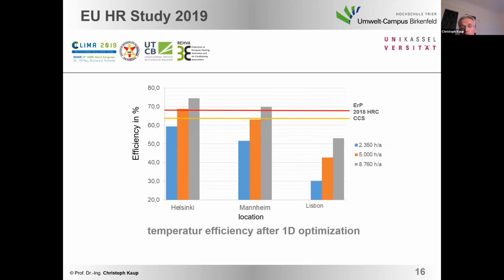But that will lead to flexible efficiencies, and that showed that a static requirement on efficiency doesn't help. So if we look here, for example, there's an error. I see that the lines are a little bit misleading. The red line should be at 73%. That's the ERP requirement, as already Davide showed us, and 68% for the cyclic compound system or run-around coil. But you see that the optimized efficiencies after 1D and even after 3D are quite different.